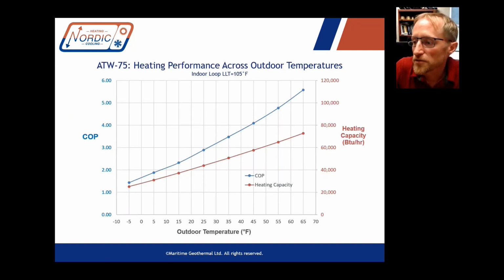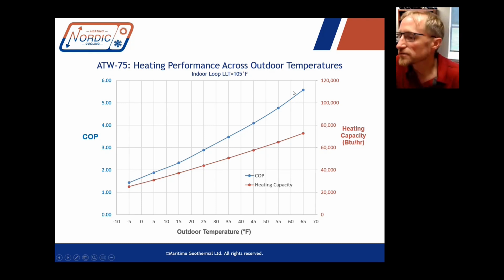As far as a curve goes, this shows how the COP and the capacity vary with the outdoor temperature. I apologize, I used to have a Celsius one in there, but I'm used to thinking in Fahrenheit, and so are our American customers. So this one is the imperial version. You can see this is pretty close to the coldest temperature here. It actually goes down to -7, but at -5, you're going to have a COP of about 1.5. And as you go up to, say, a 65-degree outdoor temperature, that can go as high as 5.5.